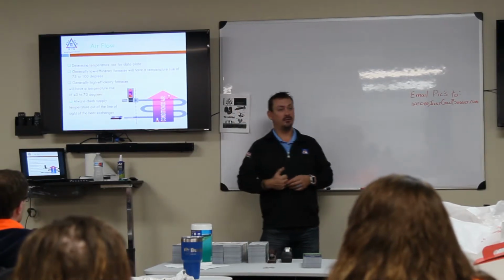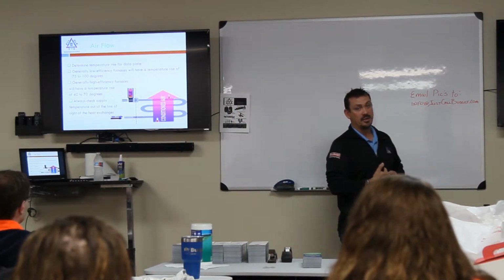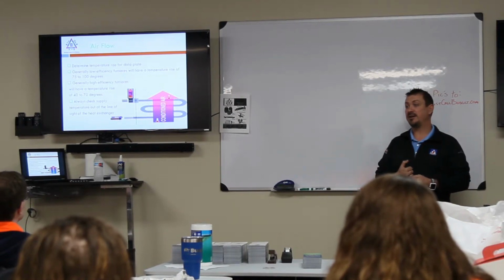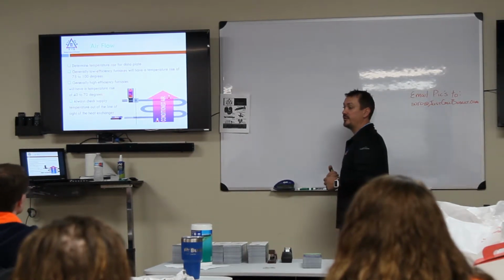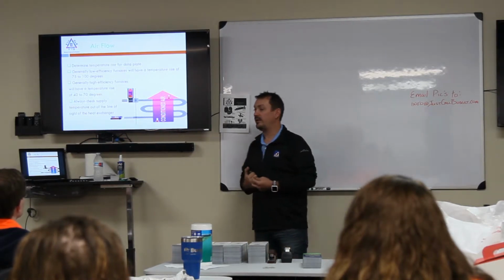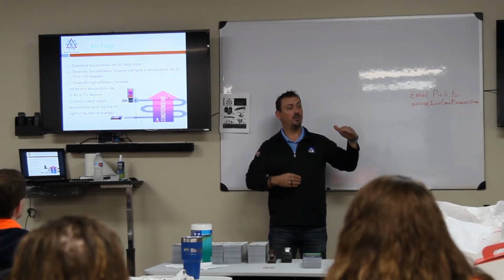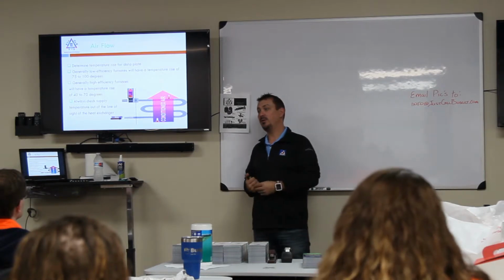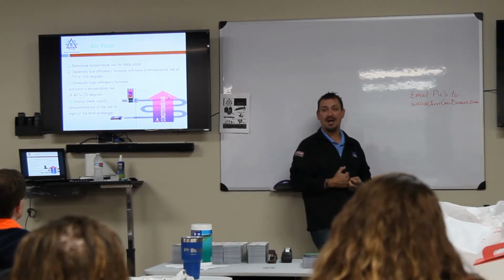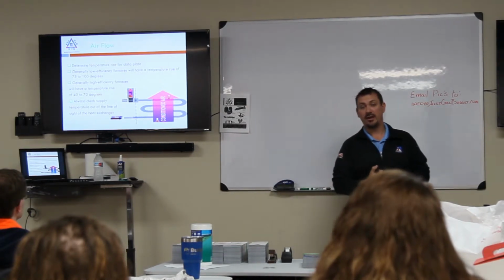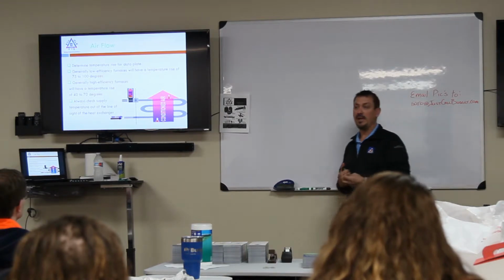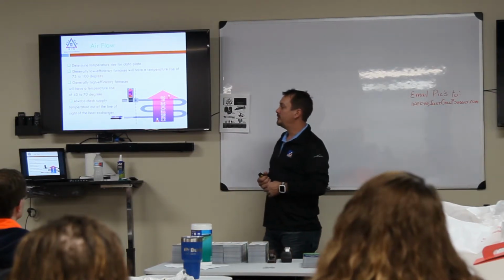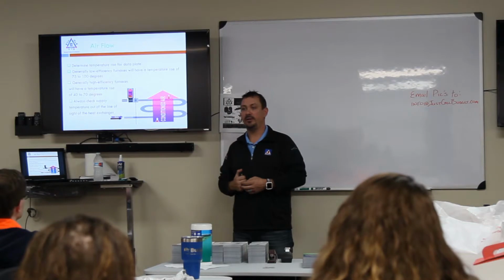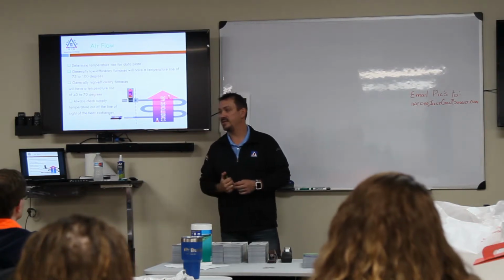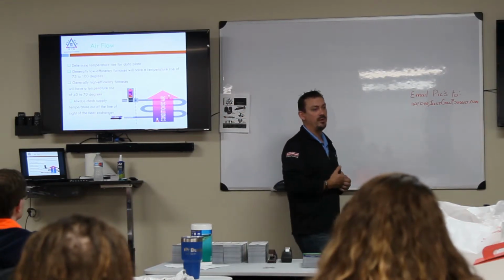Next, we're going to check for temperature rise. Temperature rise is another thing that's going to affect the life of the equipment and also the efficiency of the equipment. On every single manufacturer's data nameplate, where you can find the model number and serial number, they will have what the temperature rise is supposed to be for that equipment. And on average, you may see like 35 to 70 or 40 to 70 degrees.